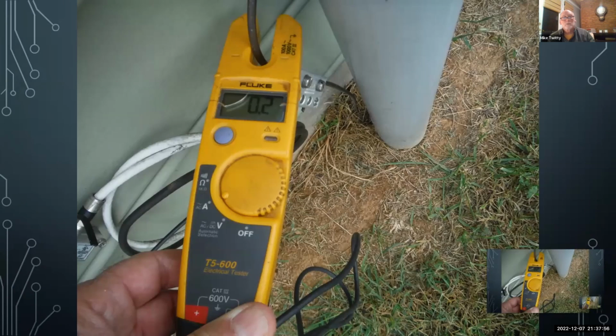Now, this is another grounding electrode conductor. This is a normal situation. Even though you don't want any current on that, it's still a parallel path because they're bonded at the service equipment, and it's going through the ground back to that transformer. So you're going to get a little bit of current on it. I mean, there's going to be some measurable current on it if there's a load on that house. This is 200 milliamps. Now, if you put some kind of load like a person, it's going to drop it because there's more resistance, but there will be some load on it because there's a parallel path. It's not a perfect system.